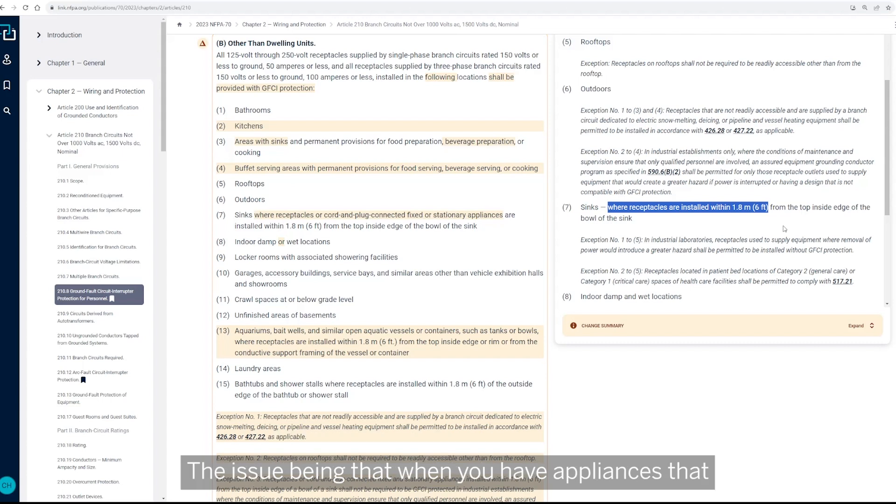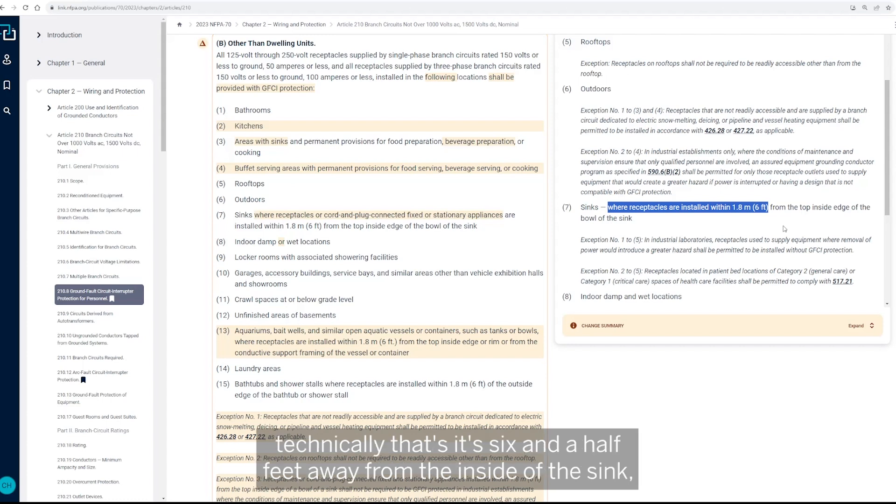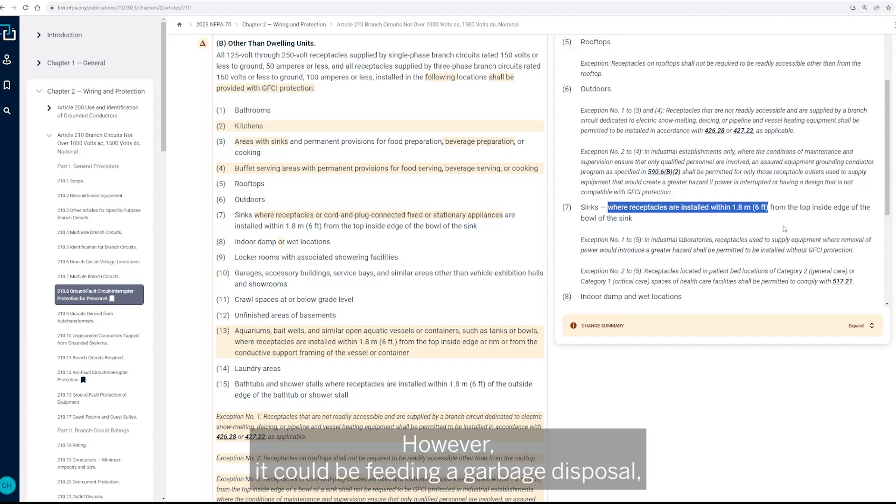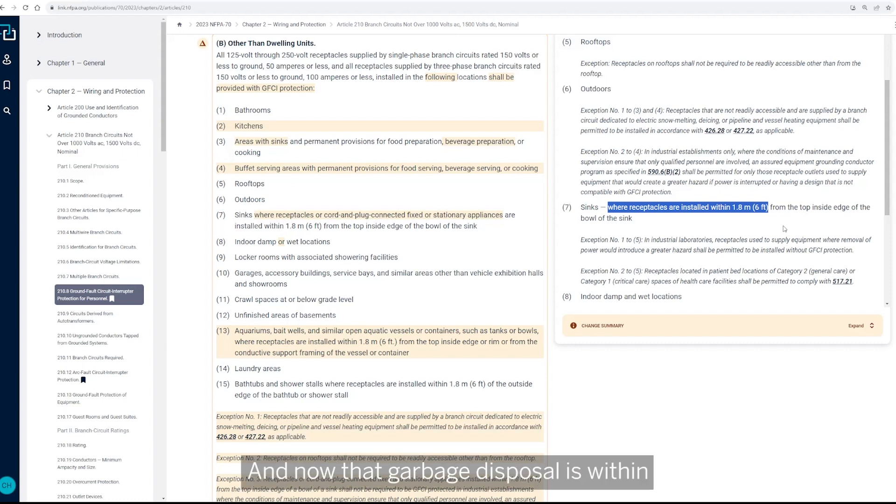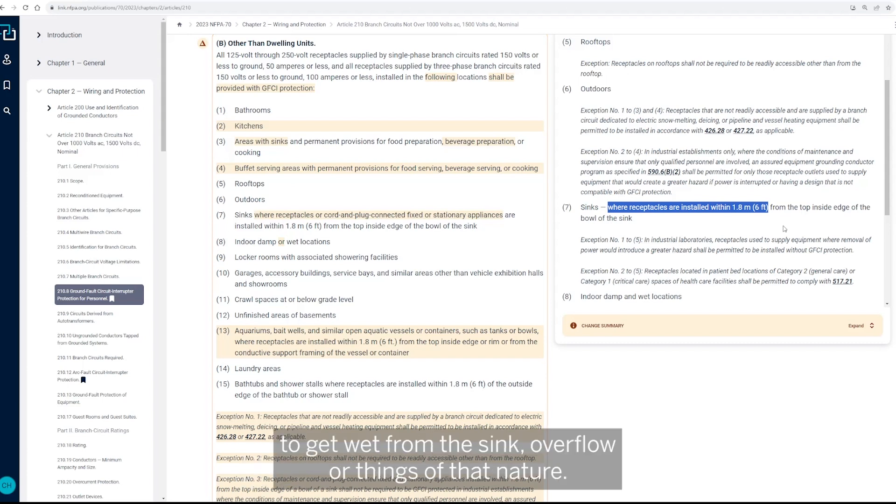The issue being that when you have appliances that have a certain length of cord, you could have the receptacle technically that's six and a half feet away from the inside of the sink, which wouldn't require GFCI protection. However, it could be feeding a garbage disposal that has a three foot cord that'll reach over. Now that garbage disposal is within six feet of the sink and subject to the potential to get wet from the sink overflow or things of that nature.